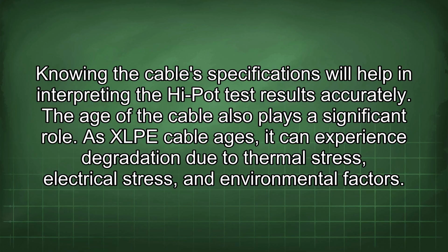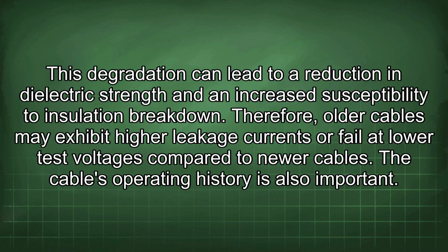As XLPE cable ages, it could experience degradation due to thermal stress, electrical stress, and environmental factors. This degradation can lead to a reduction in dielectric strength and increased susceptibility to insulation breakdown. Therefore, older cables may exhibit higher leakage currents or fail at lower test voltages compared to newer cables.